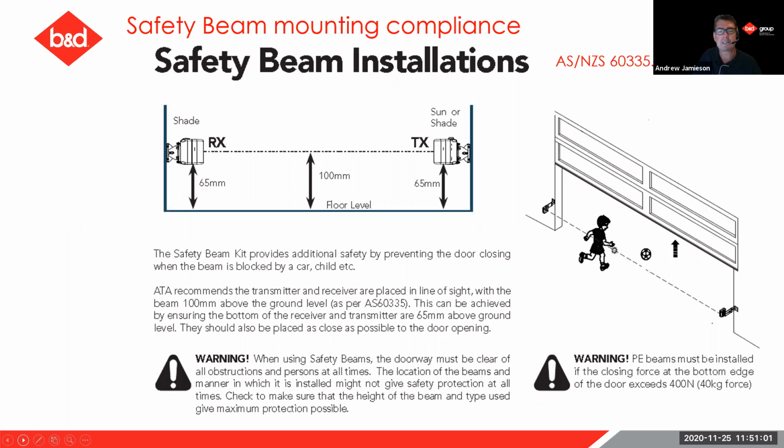You'll also notice that it's actually to the beam itself, to the infrared beam itself. So the way that we generate that is from the deck to the bottom of the beam, 65 mil, and then it naturally falls the infrared eye sensor across the opening to 100 mil. So measure from 65 mil to the base of the unit, and we will achieve 100 mil. We also start talking about that other area, which is part of that 60335, which is that 40 kilo leading edge maximum force on those bigger doors.